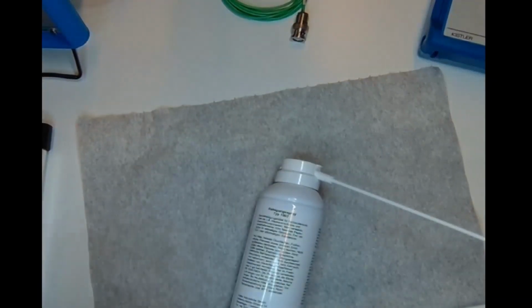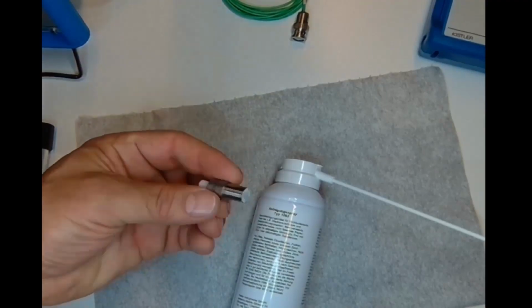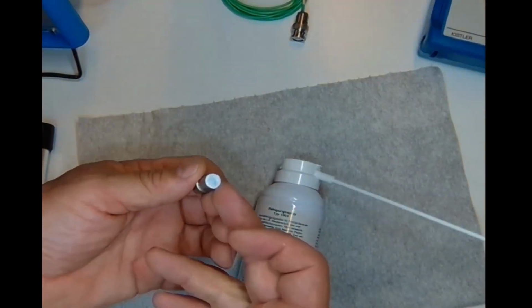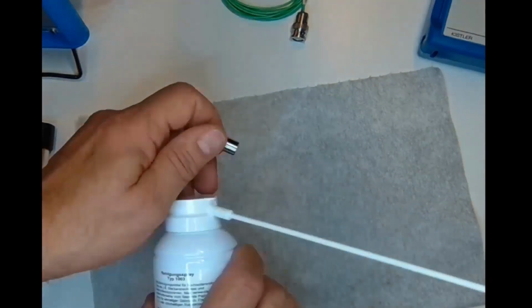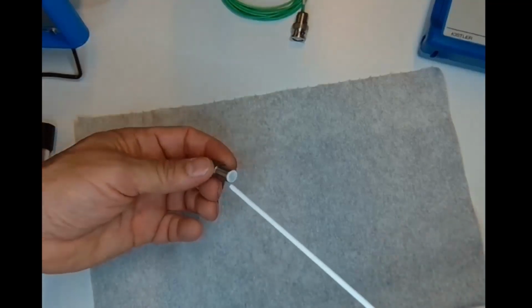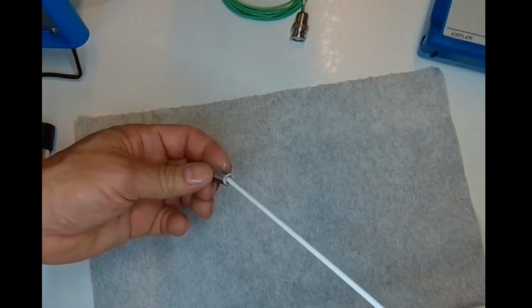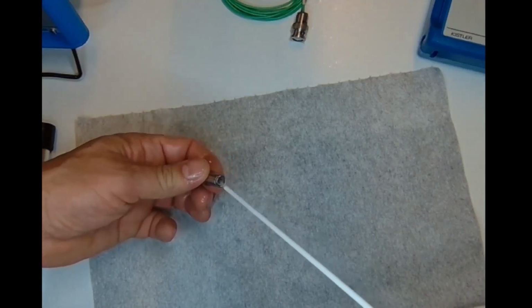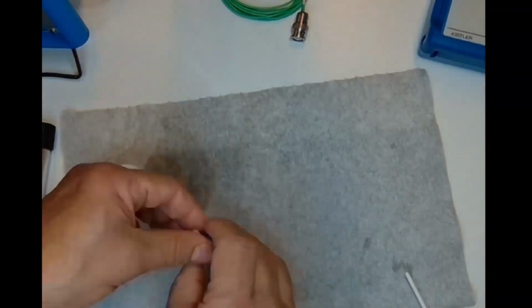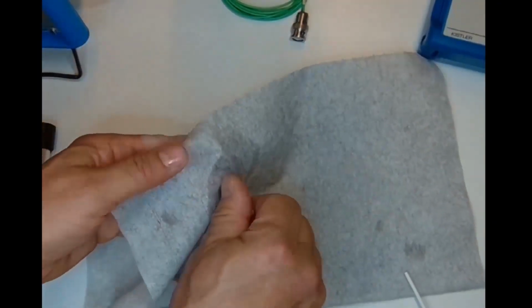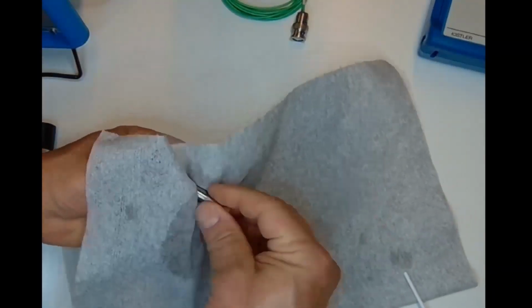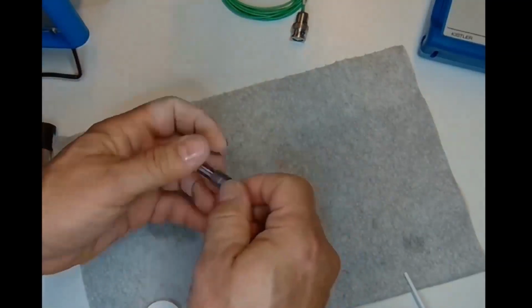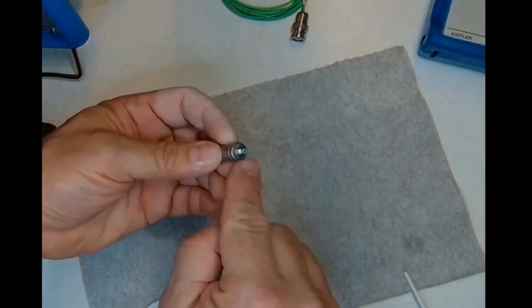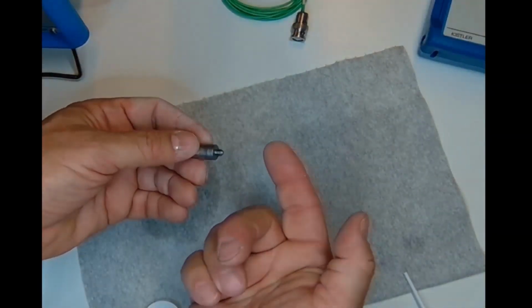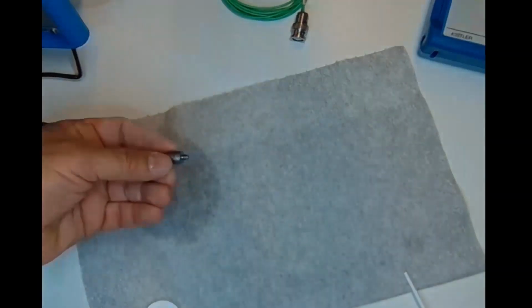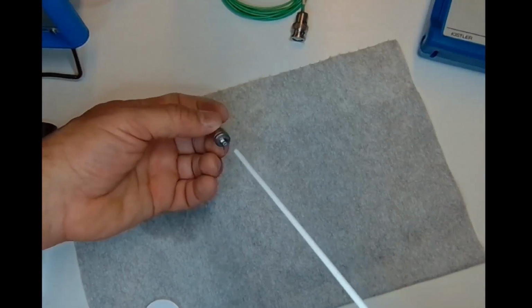So this is the situation which should not remain. The covering of the sensor by the grease is only for the measurement purposes. After the measurement, you have to clean the membrane properly. Really use a sufficient amount of the cleaning spray, of the detergent, to clean the sensor properly. Use some kind of non-woven textile to really clean the sensor membrane. And the same should be done with the connector. Never touch the sensor with dirty hands like this. Never ever. If it happens, clean this connector.